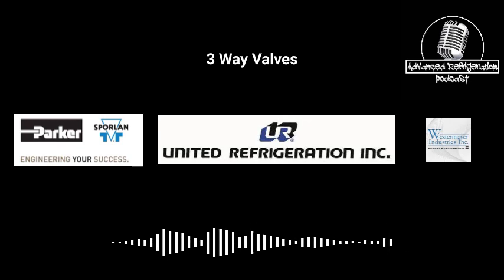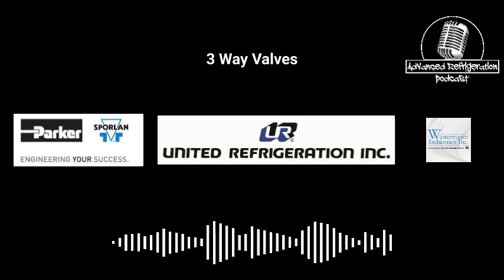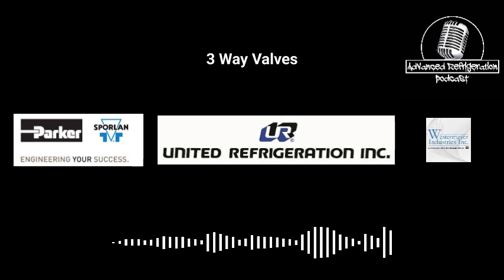But the MTWA or whatever, the bipolar three-way valves, we've rebuilt I think 3 or 4 of them now at this point, and they keep sealing. We haven't had a problem. I don't know at what point it will not seal with just brand new gaskets, if that makes sense. I always get 2 sets of gaskets because I'm paranoid about it, because I had one where we did it and it leaked. Oh no. And it was leaking worse than when we took it apart.